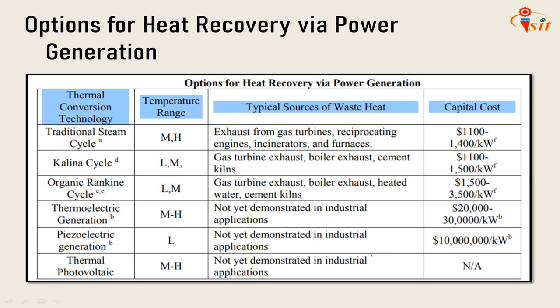Now, for the options for heat recovery via power generation, we will go first to the steam Rankine cycle. The most frequently used system for power generation from waste heat involves using the heat to generate steam, which then drives a steam turbine. A schematic of waste heat recovery is shown in the figure. The traditional steam Rankine cycle is the most efficient option for waste heat recovery from exhaust streams with temperature above 650 to 700 degrees Fahrenheit. It is around 340 to 370 degrees Celsius.